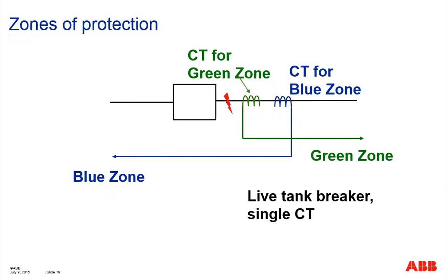If the breaker is normally open, what are you going to do? The blue zone will still operate, unnecessarily overtripping. It doesn't really need to open, but it has to because the fault is in the blue zone. However, with the breaker open, the green zone will still restrain. So even with the breaker open in this condition, the blue zone overtrips without really clearing the fault, so it really doesn't help alleviate the fault stability problem.